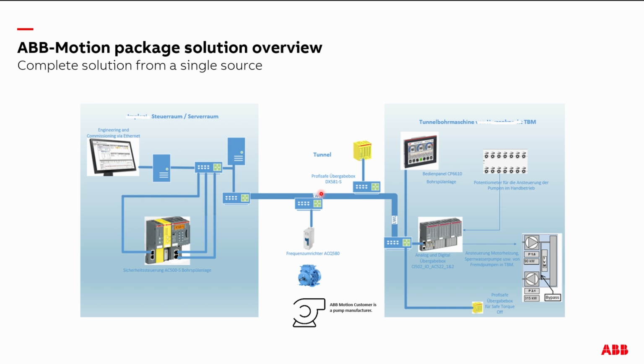This system includes his own pump with an ABB squirrel cage motor, an ABB ACQ 580, and a peripheral I/O box, whose duty is to receive emergency stop commands via mushroom buttons and via ProfiSafe, then switch off or stop the pump first in a controlled manner, and go into safe torque off status.